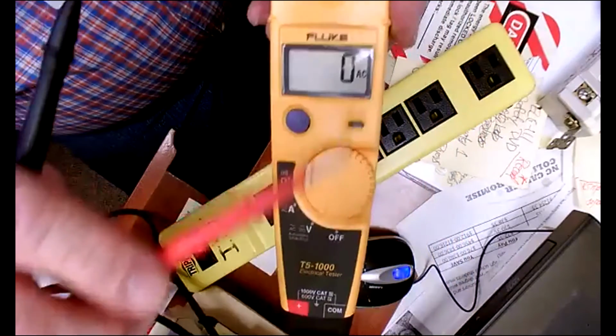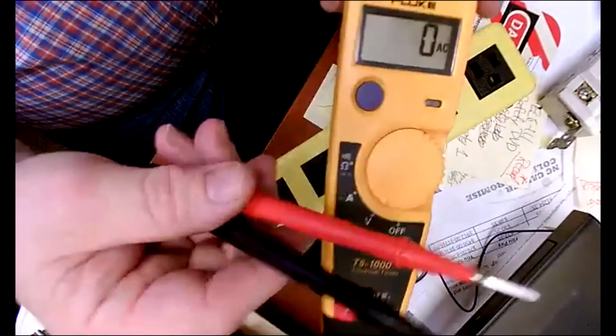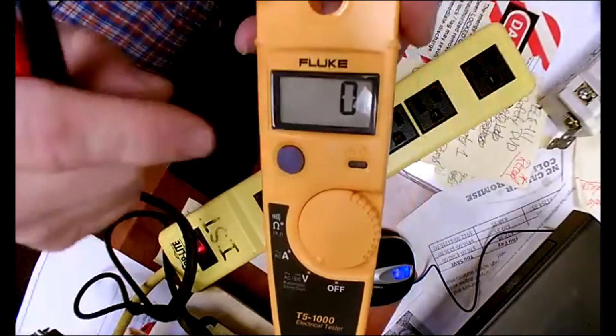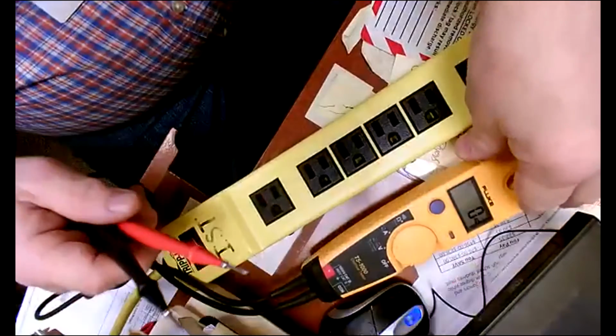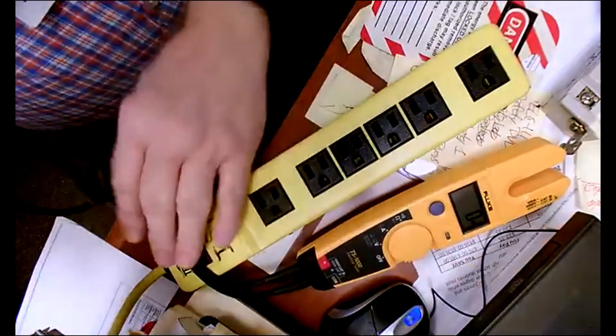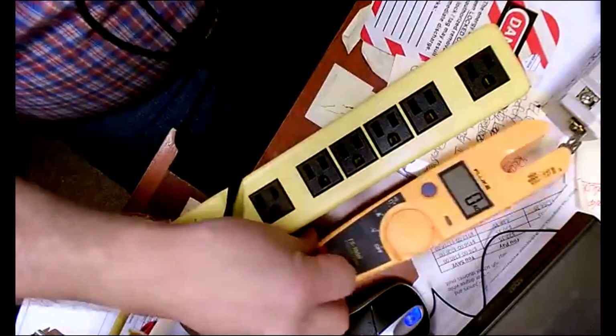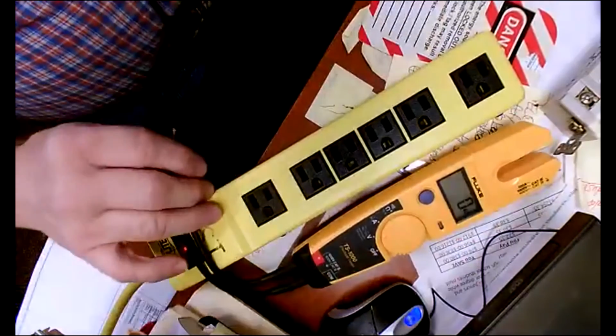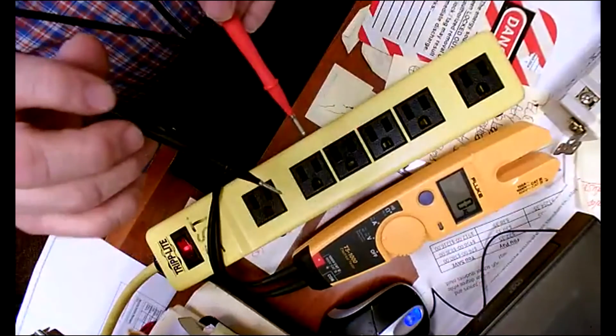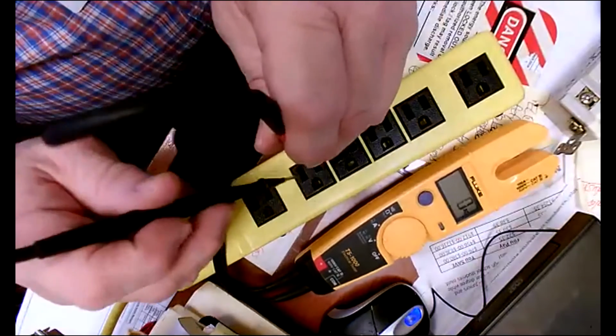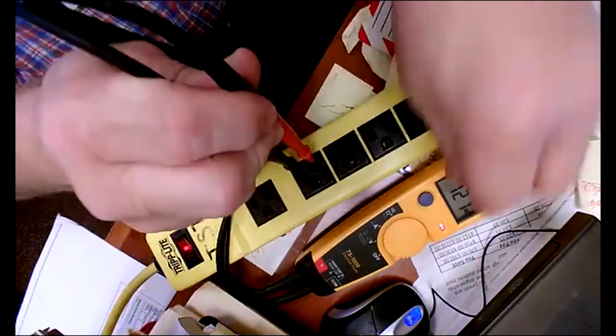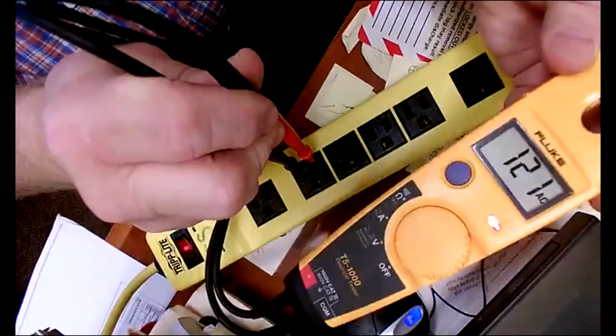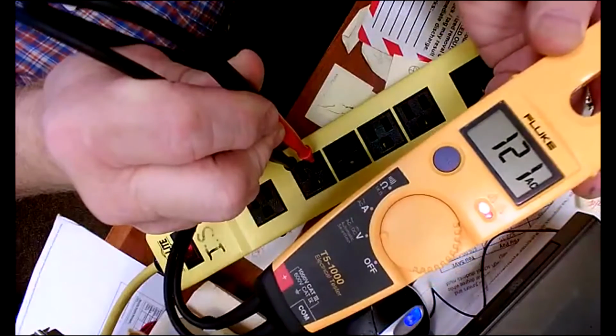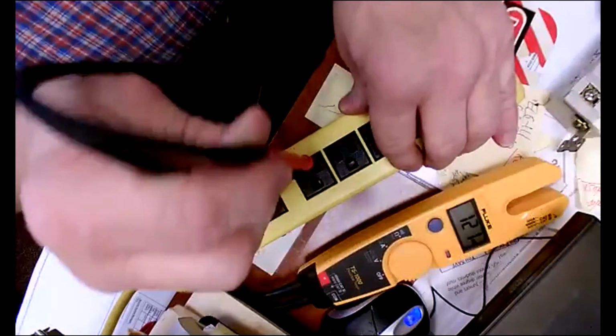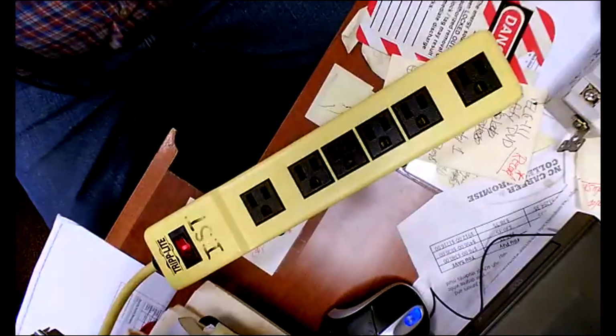Right now it's saying AC, but if you come in contact with DC, like on a forklift or a car battery, it'll switch and tell you that it's DC up there. It knows. Okay. So let's go here, and we're going to check a receptacle that we know is hot, and we're going to make sure the meter's okay, because just because the meter was good last time we used it doesn't mean it's good today, right? It may not be. So we're going to go to our hot terminal and to our neutral and measure that. And what does the meter say? 120 volts. Well, 121. 121 AC. So now you take your meter and then you go out to where you've locked out that panel.